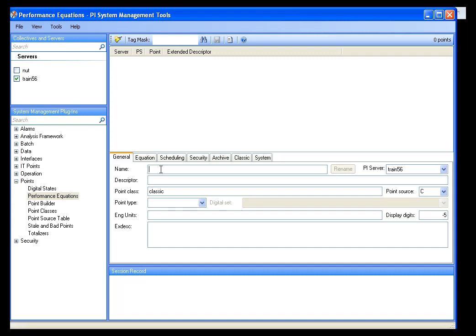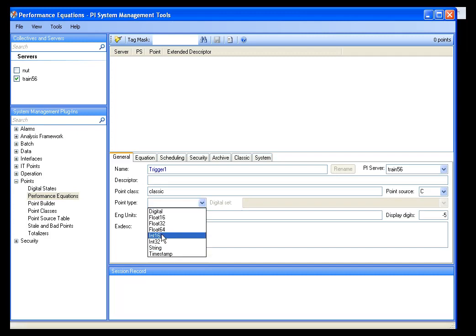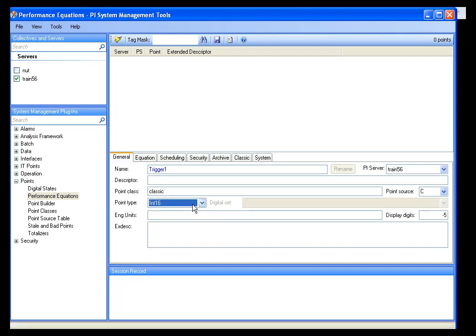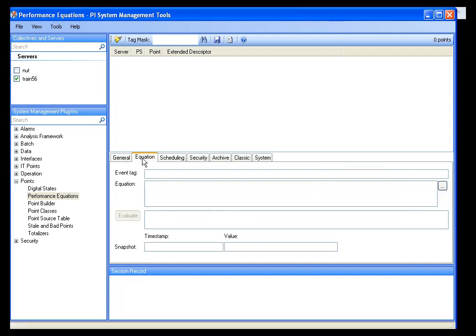In this case, I'm going to use a temperature tag, and I want to define my batch start when the temperature goes over an ambient temperature. Let's say the ambient temperature is 80 degrees. I'm going to call this trigger1, and it's actually going to be an integer — I'll call this an int16 — and the point source is already pointing to my performance equation engine. I can click on the equation tab here, and my equation is simply going to be CDT158 is greater than 80. That's a temperature tag.